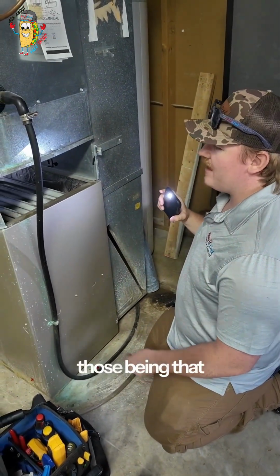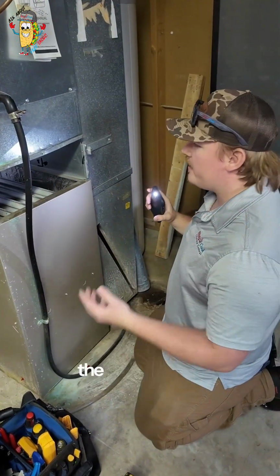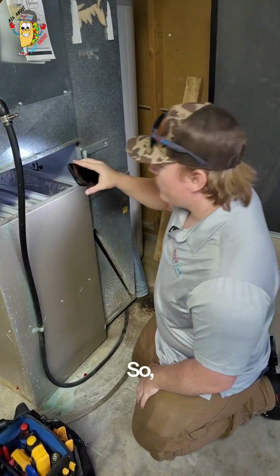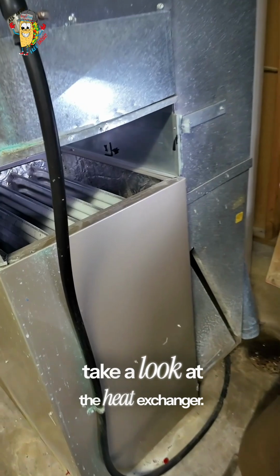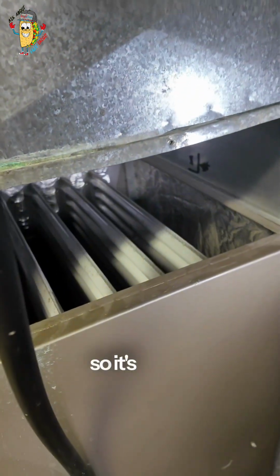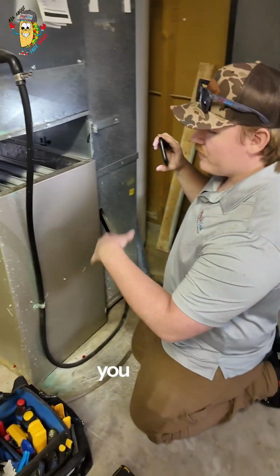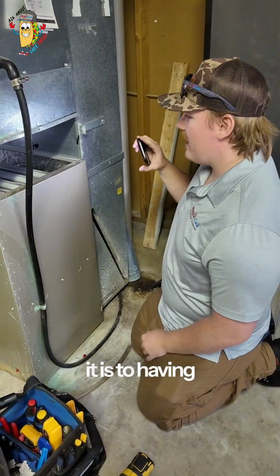While doing our furnace inspection, we noticed a few different symptoms of issues with the heat exchanger. Those being that the temperature rise was very high and the flames were flickering orange. So, we decided to get in here and take a look at the heat exchanger. This furnace is from 2011, so it's about 14 years old as well. The longer a furnace has been around, the more prone it is to having these issues.